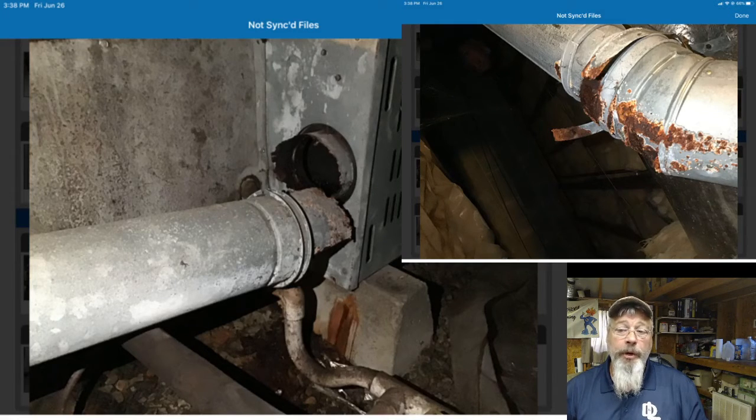Customer complained that they were getting headaches frequently in the wintertime. Well, guess what? Because the carbon monoxide levels were getting so high in the home, it was causing headaches in people, in the tenants. This house does not have a safety device in it. The safety device that would have triggered this would have been a carbon monoxide detector.